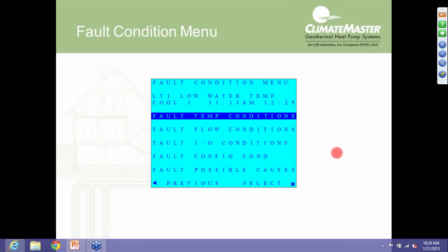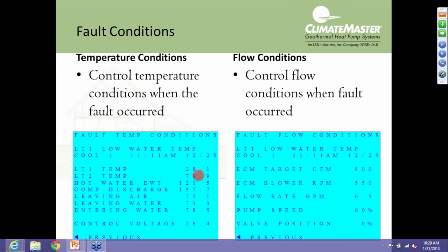So we can look here at all our temperatures at the time of the fault. Here's LT1, 28.1 degrees. Well, if the jumper's not cut, it locks out at 30 degrees, and we're just a little bit under that. Again, it's got to see it for 120 seconds upon initial startup, so it could drive just slightly below that, and it looks like it's doing what it was supposed to do, just from what we see right here.